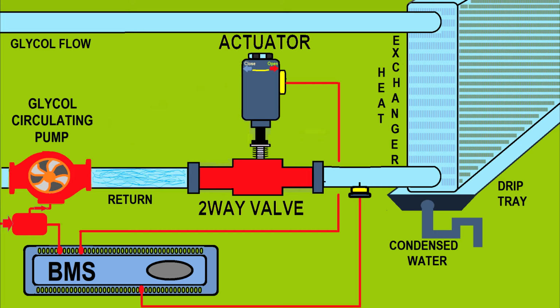rather than bypassing it. If you're not interlocking the actuator, a bad situation can occur. If the valve is broken, like in this case, you will starve the pump. You see, in between the actuator and the pump, you will have a lot of bubbles and negative pressure, and you can burn the pump. The pump will get red hot.